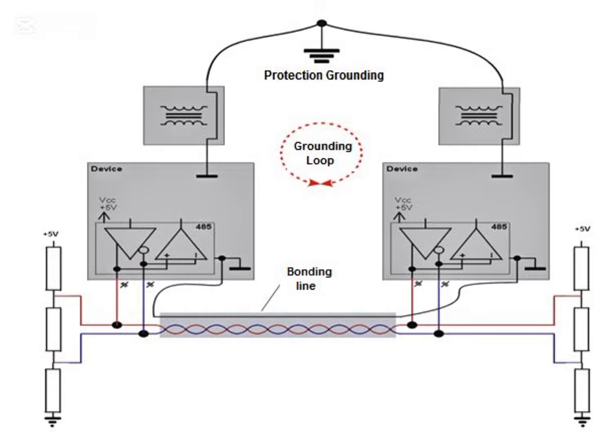2. Grounding, reference ground. Purpose: establishes a common reference, 0.0 volts, for electrical circuits, to ensure signal integrity and reduce noise. Applications: signal ground used in instrumentation, for example, PLCs, DCS, sensors, to provide a stable reference. DC power ground used in control systems to avoid floating voltages. Shield grounding prevents EMI by grounding cable shields at one end.